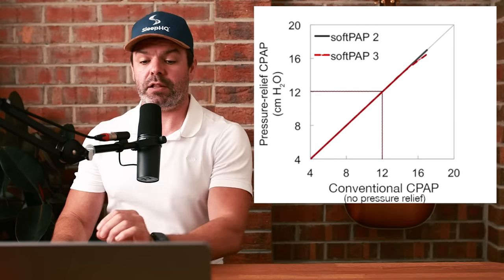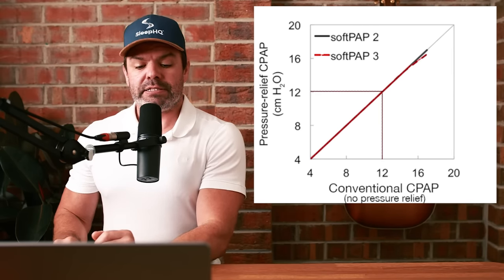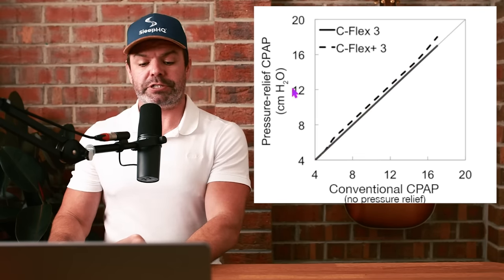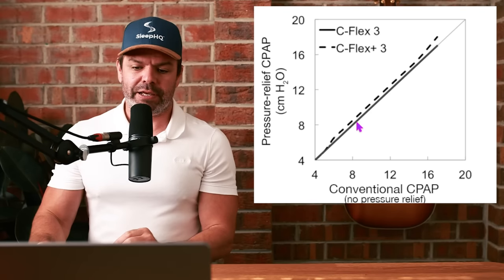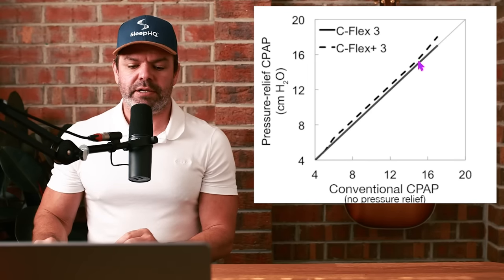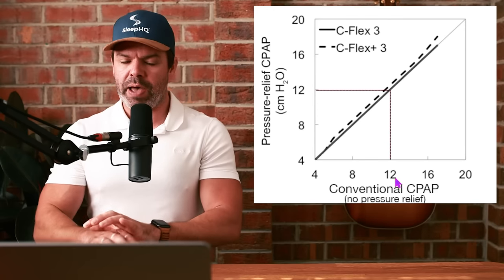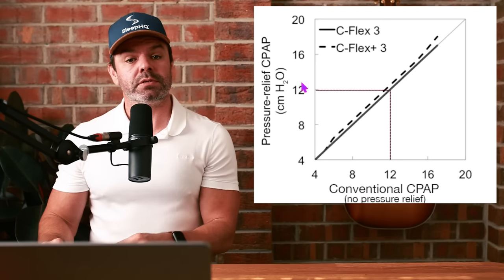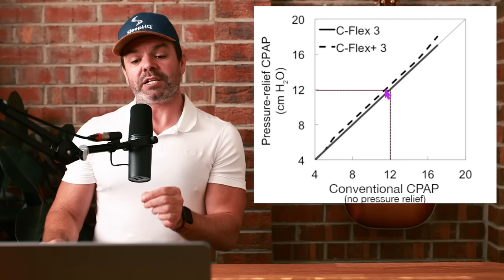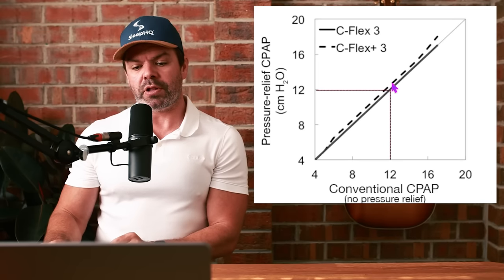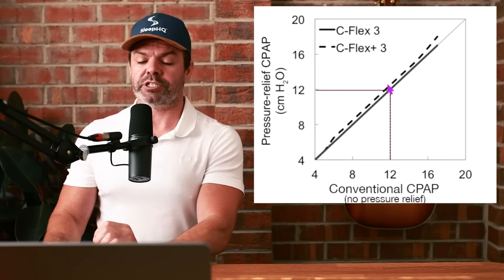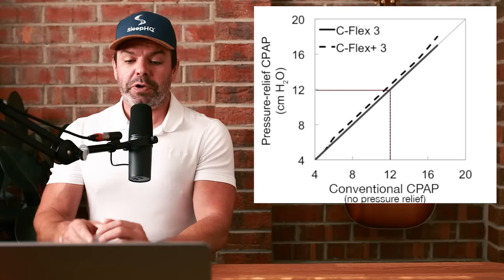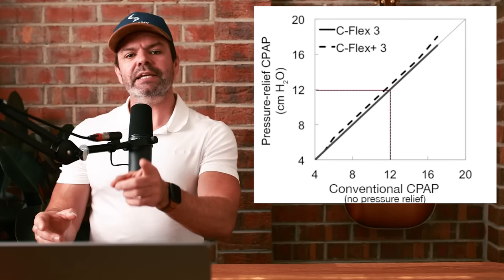Let's also look at the Philips Respironics and their C-Flex pressure relief. Once again, same chart, lines very close together. You can see 12 centimeters with conventional CPAP no pressure relief is pretty much lining up with 12 centimeters with C-Flex on three. With C-Flex Plus on three, you can see the dotted line here, you need just a little bit extra pressure when you add that pressure relief, but very, very good.